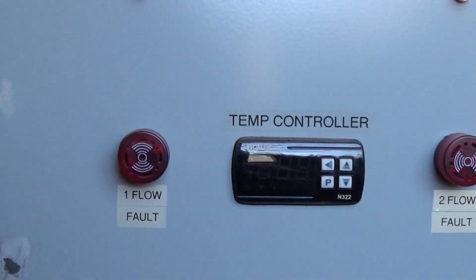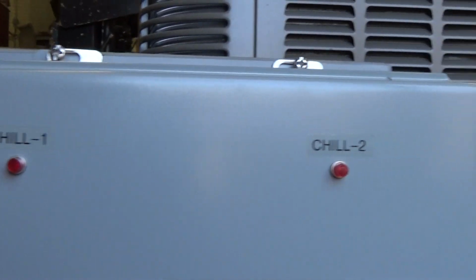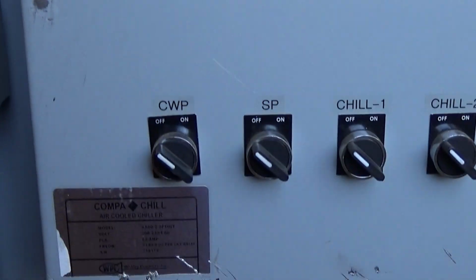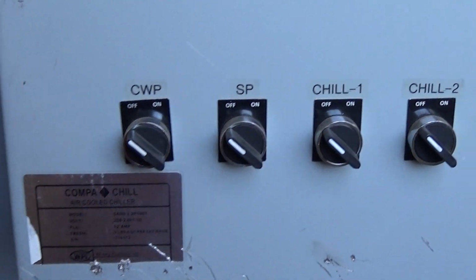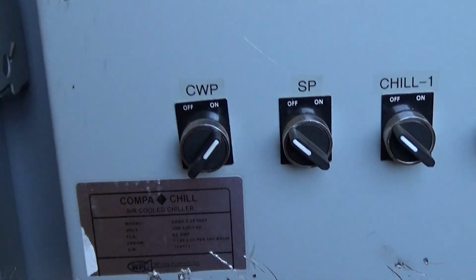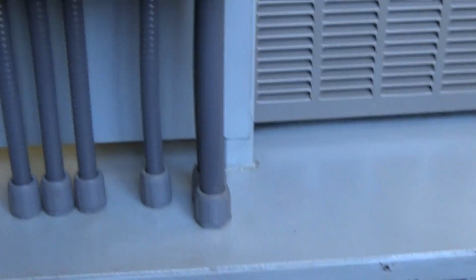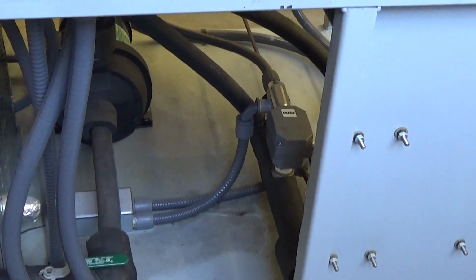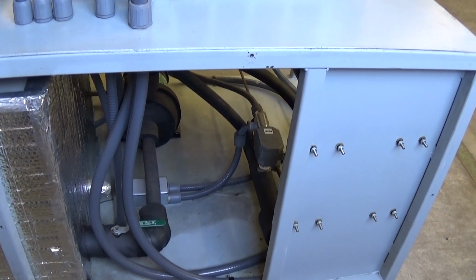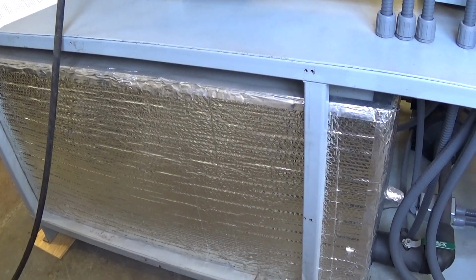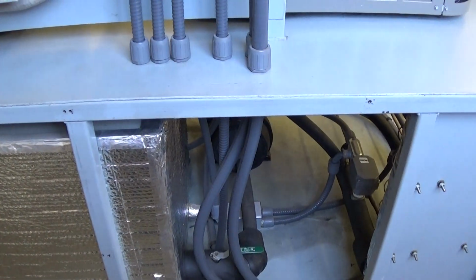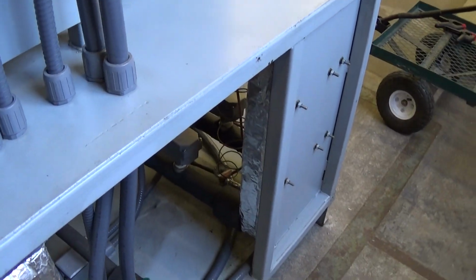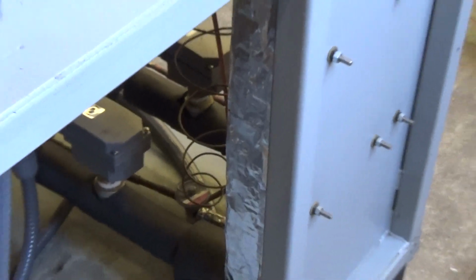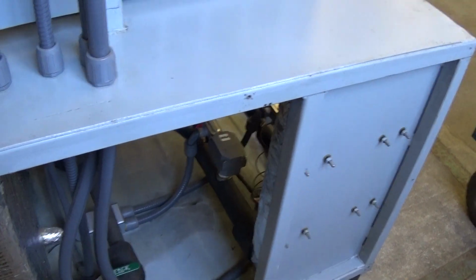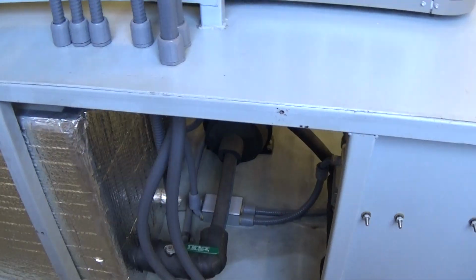And then we have our controller. We have the flow fault alarms. And we just have these indicator lights here also. So the first thing you do is turn your chilled water pump on. So then we have our 1/2 horsepower chiller loop pump on. And again, that's just circulating the glycol from this nice sizable insulated glycol reservoir through the 2 exchangers, evaporators, all the time. Set it and forget it. Actually, you don't really have to set anything.